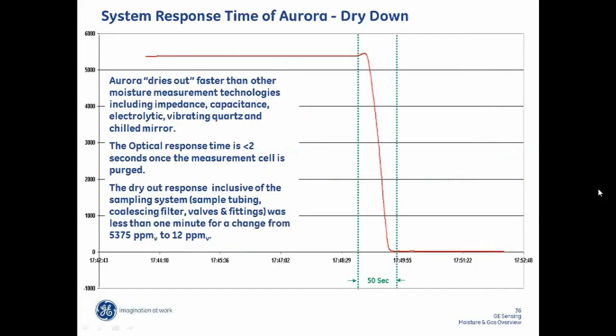One of our customers wanted to test a process upset. So in the field, they injected water into a natural gas system, and the system immediately spiked and returned back to normal, fully back to the original value within 7 minutes and within 2 ppm of the original reading in 2 minutes. So again, if this were other technologies, this would take several hours to recover, if not overnight.